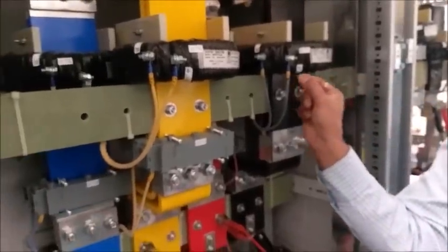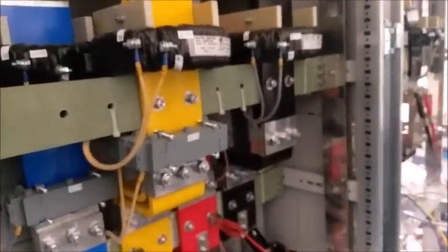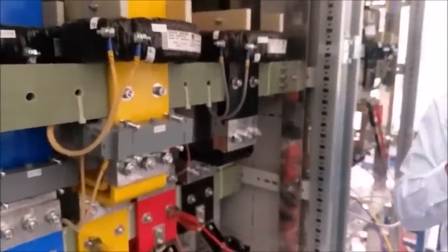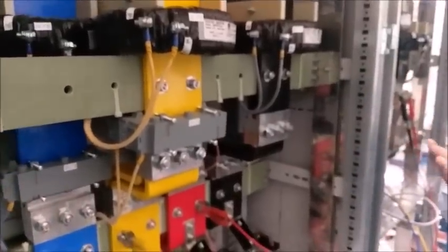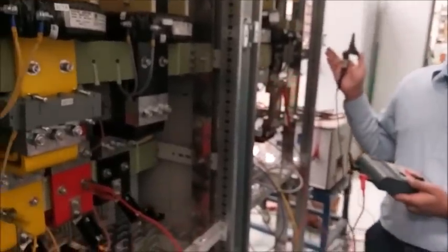But what happens is, there can be a very small connection also. Suppose one strand of wire is connected here by mistake, so it will show continuity. But in the Megger, it will directly fail, because through that link it will show that the insulation has failed. So we are doing this test for all, with respect to each phase and the rest.